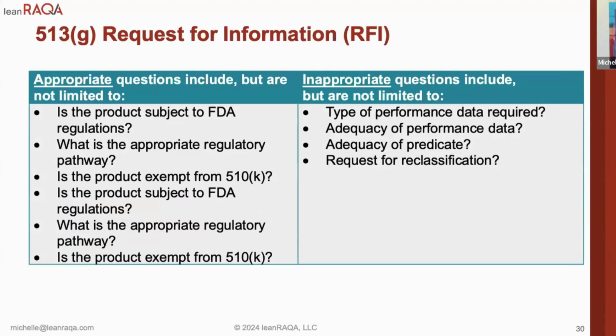You would ask this question in the event that, say, the product code that exists for it is class 1 510K exempt, but maybe you have different technological features, or you added software or something of that nature, or an indication, and that might have taken you out of what FDA intended for the exemptions around that product. Is the product subject to FDA regulations at all?